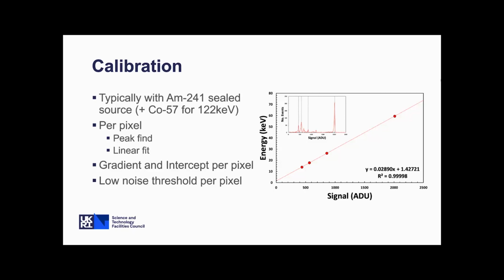To calibrate the detector, we typically use an americium source, or maybe a cobalt 57 source if there are higher energy applications as well. We do this on a per pixel basis. So we find the peak positions of these 4 peaks from the spectrum. We do a linear fit, and that linear fit gives us a gradient and intercept, which we apply to the data, and also a low energy threshold per pixel.